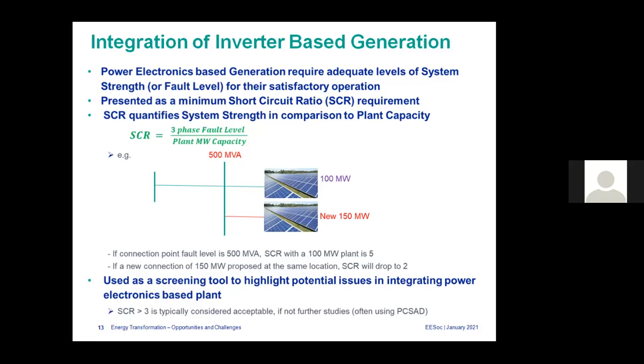But if it is less than 3, or even less than 2, they say you probably have to do studies and model to see what will happen. Normally, if it is less than 2, they don't guarantee correct operation for different contingencies. Because if there is a fault in the system, you don't expect the solar farm to trip as well. Normally hydro generators or thermal generators don't trip unless the fault is very near the generator, or within the generating system. You don't expect generators to trip for system faults.